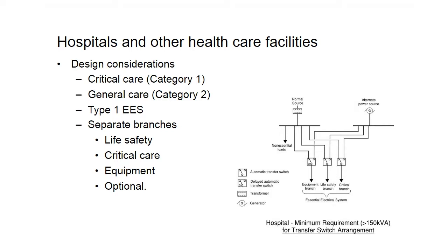These are comprised of branches. The three that are required by code are the life safety branch. This is generally serving loads such as exit and egress lighting, your med gas alarms, elevator cab lighting, generator loads, so like your battery charger, fuel pumps, ventilation systems that serve the generator load. The key thing to remember here is that the life safety branch also needs to meet the requirements of Article 700 in the NEC, except as amended by Article 517, specifically to healthcare environments.